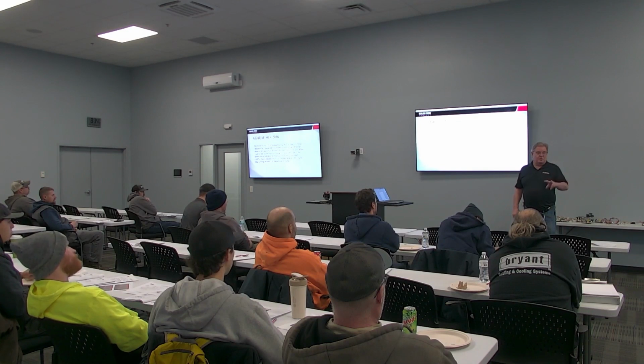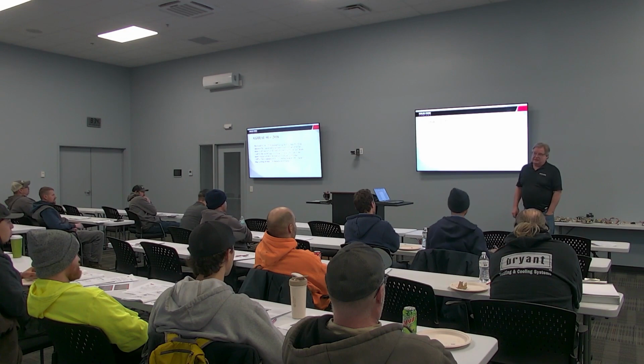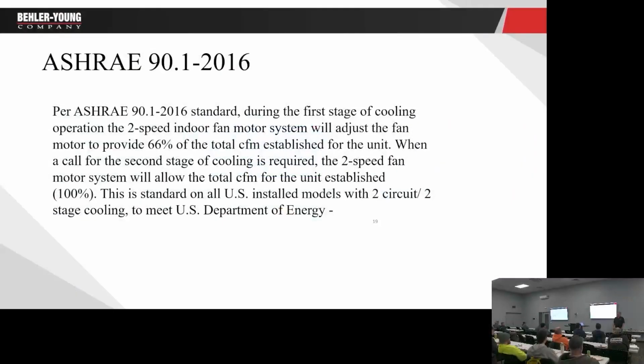Okay. So we have the ASHRAE 90.1 2016, which says if you have over a 2,000 CFM blower, it needs to be 2-speed. Because in a commercial building, we have to have the blower running all the time. That's by code. You have to have circulation all the time. So what this code said is, if we're running the blower all the time, it uses a lot of electricity to run that blower at full speed all the time. So we're going to run the blower at a lower speed for circulation. That's what this code said. So if you're working on a 5-ton or smaller, it's going to be a single-speed blower. If you're working on a unit bigger than 5-ton, over 2,000 CFM, it'll be a 2-speed blower.